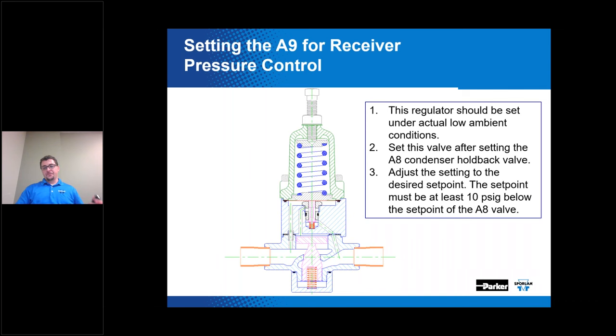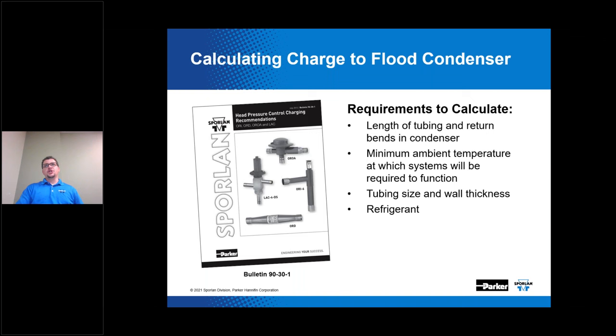When condenser flooding is used for head pressure control, extra refrigerant is stacked up in the condenser during winter operation, and that extra refrigerant has to go somewhere in the summer. This is where the receiver becomes critical. Valve side head pressure control requires a receiver, and it has to be properly sized. Our tech support team gets calls from time to time about head pressure control valves not operating properly, and we find there's no receiver on the system — that's a problem.